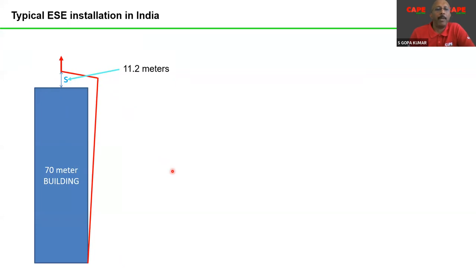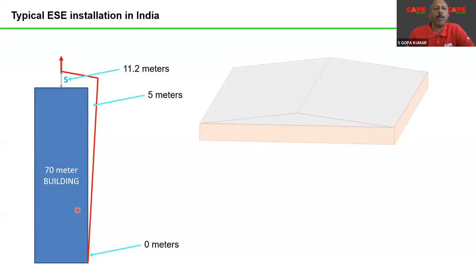That means you have to have some kind of isolated material between the red line and the building. The red line is nothing but the parts of lightning protection. And the distance keeps on reducing as we reach towards the bottom, for example, 5 meters, and at the bottom of the building, 0 meters, if equipotential bonding is made. If it is not made, of course, all these calculations are wrong.